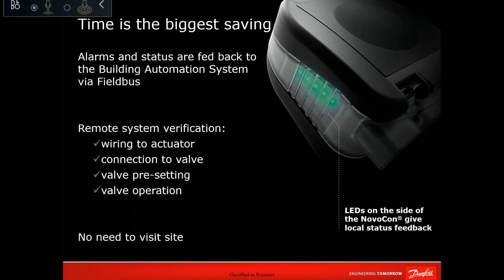So if you have issues in setting the valve, or it's used or a retrofit, and you want to put this Novocon on an existing ABQM, then you can make a user-defined valve and set the stroke length. You don't have to set the flow, not to confuse. You just say that I need to limit my stroke to that limit, and that's it. So it's flexible. You don't have to set anything mechanically.